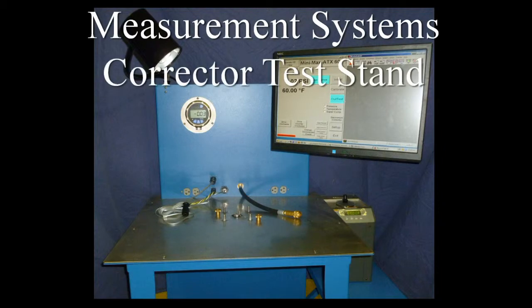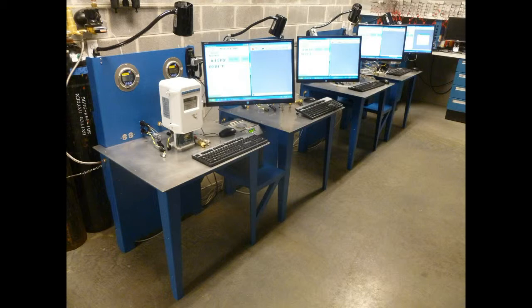The Measurement Systems Corrector test stand is a self-contained, automated pressure and temperature corrector proving system. It is capable of testing any Mercury or Honeywell corrector up to 300 psi at 3 user programmable pressures for both in-test and out-test with the press of a button.